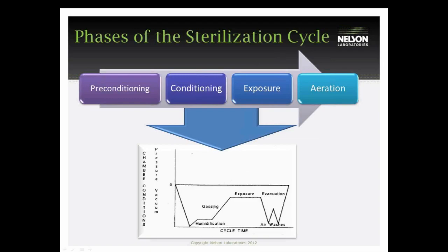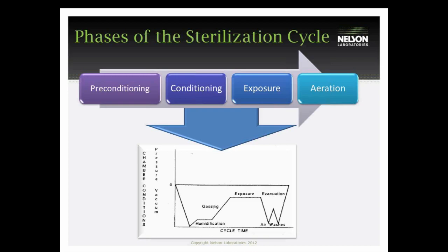There are four phases of the sterilization process. The preconditioning phase is typically held in a separate preconditioning room and can be anywhere from 12 to 24 hours. After the preconditioning phase, the product moves into the sterilizer, where you get your conditioning and exposure phases. Then it will be removed and placed into aeration. The heated aeration portion is important for the degassing of the product for residual purposes.